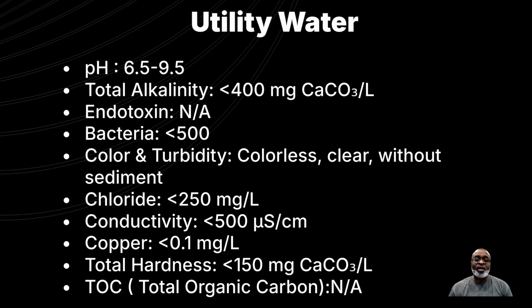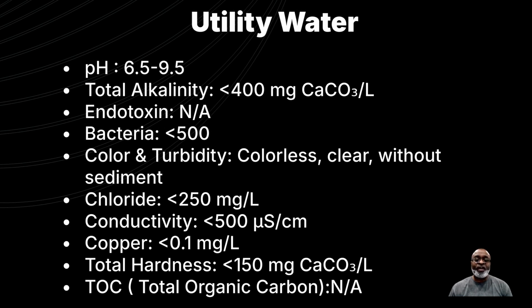Utility water is used for non-critical cleaning and must meet the following limits. pH 6.5 to 9.5. Total alkalinity, less than 400 milligrams per liter of calcium carbonate. Endotoxin, not applicable for utility water. Bacteria should be less than 500. Color and turbidity. The water must be colorless, clear, and free from sediment. Chloride, limited to less than 250 milligrams per liter. Conductivity, must not exceed 500 microsiemens per centimeter. Copper, limited to less than 0.1 milligrams per liter. Total hardness, capped at 150 milligrams per liter of calcium carbonate. Total organic carbon, TOC, is not applicable to utility water. These parameters ensure that treated utility water provides a clean and reliable foundation for medical device cleaning processes, supporting compliance with ST108.